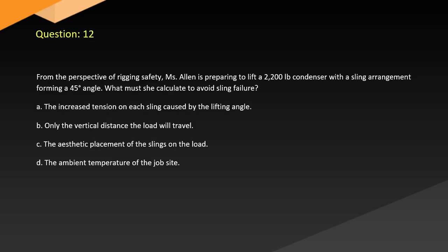Question 12. From the perspective of rigging safety, Alan is preparing to lift a 2200 lb condenser with a sling arrangement forming a 45-degree angle. What must she calculate to avoid sling failure? A. The increased tension on each sling caused by the lifting angle. B. Only the vertical distance the load will travel. C. The aesthetic placement of the slings on the load. D. The ambient temperature of the job site.